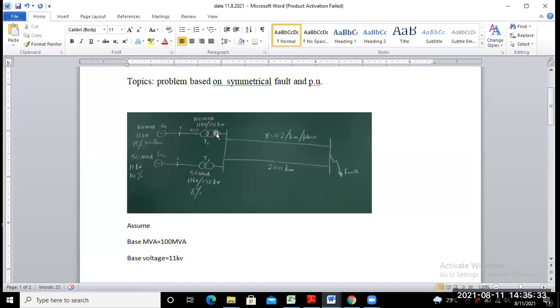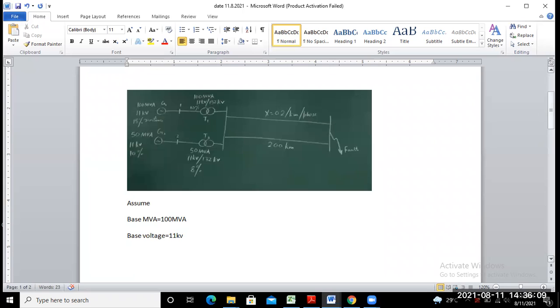Yes, sir. Okay. So 11 kilovolt we can assume up to the transformer primary side. Whenever we find any reactance value up to the transformer primary side, then we can choose base voltage as 11 kilovolt. Is it not? And after that, if you find any per unit reactance value, then you require to choose 132 kilovolt as base voltage. So just here mark the 11 kilovolt base voltage up to the low voltage side of the transformer.